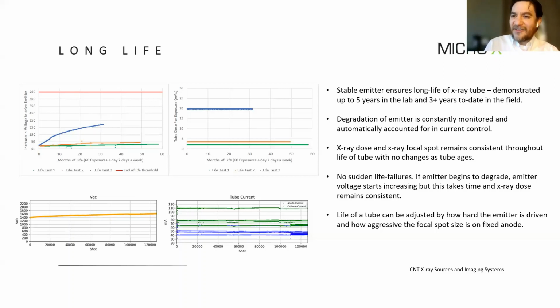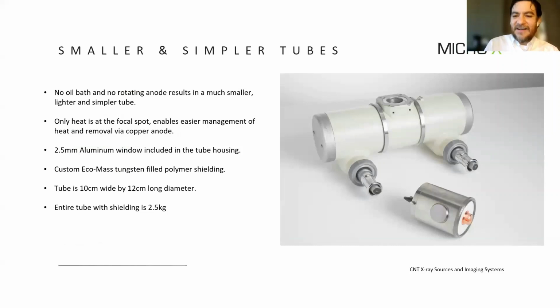So that long life and predictability is another advantage in the system. And then finally, overall, we leverage these to make a smaller and simpler tube. As I mentioned before, we manage the heat by varying the focal spot. That means we don't use a rotating anode to get quite high current and dose out of a small X-ray tube. And the field emission is cold cathode, which means that there's no heat in the filament.